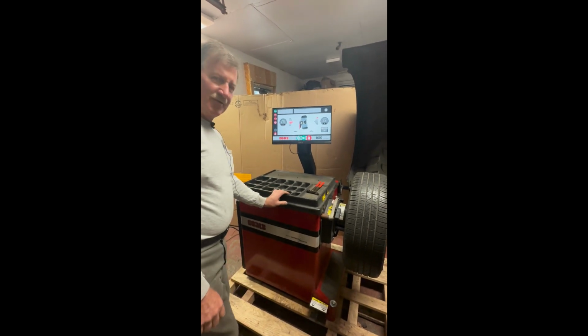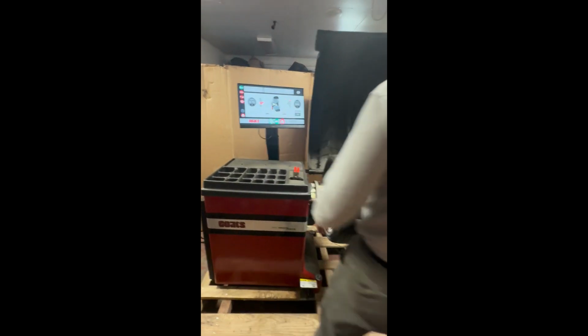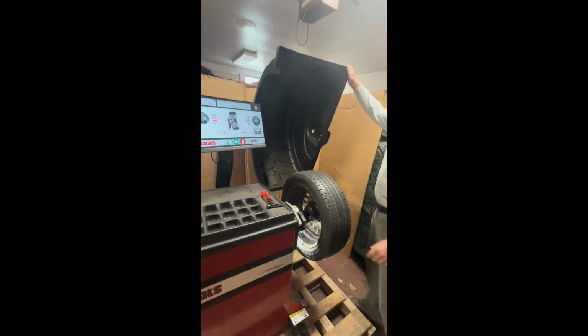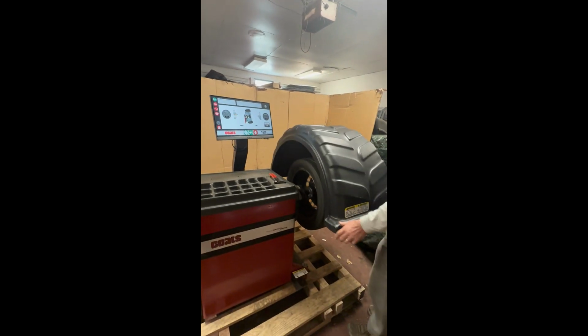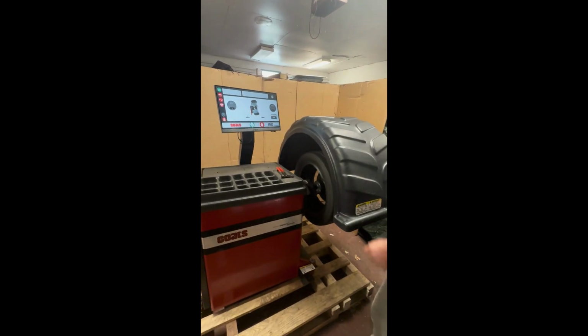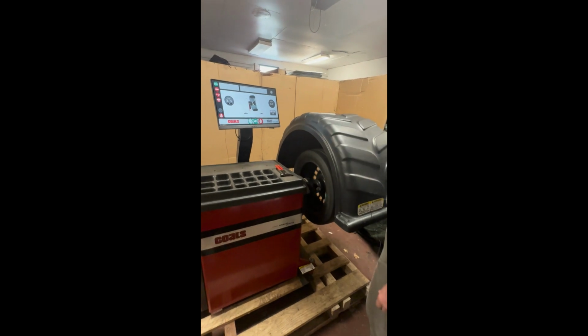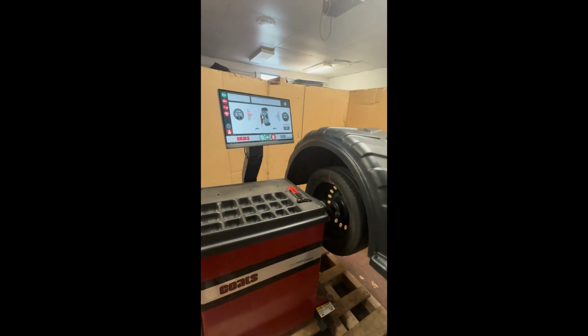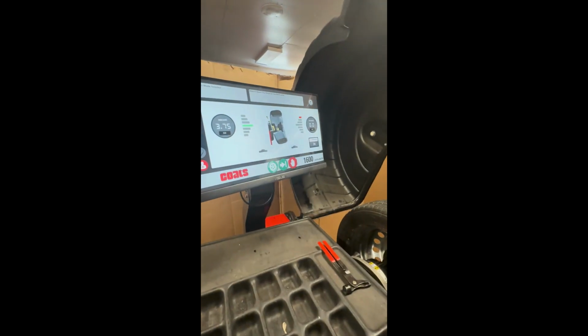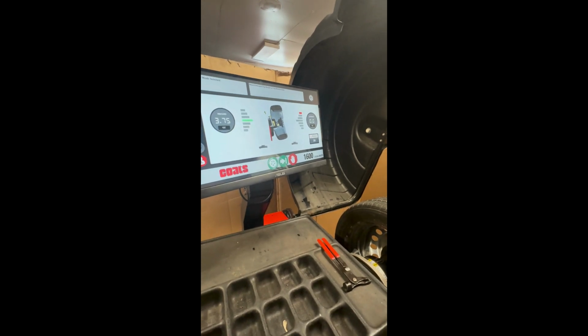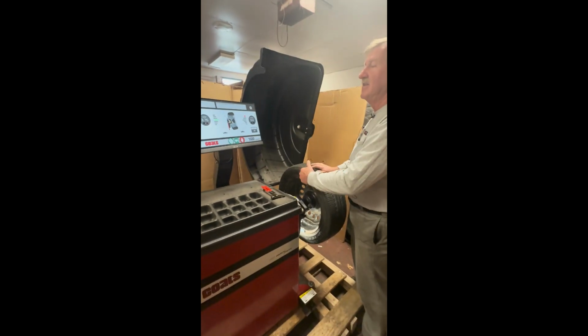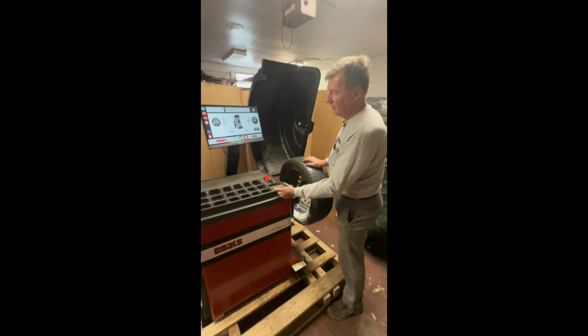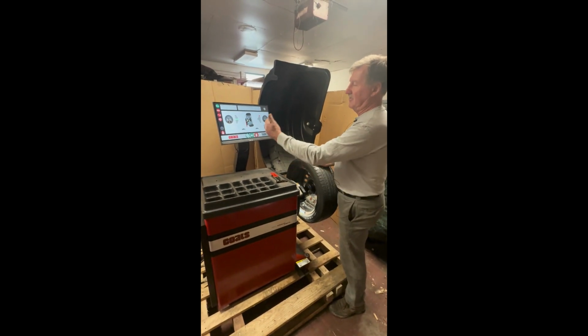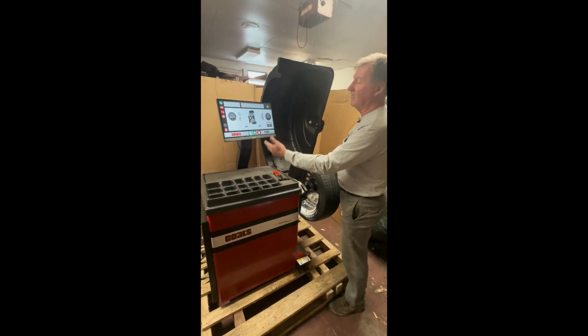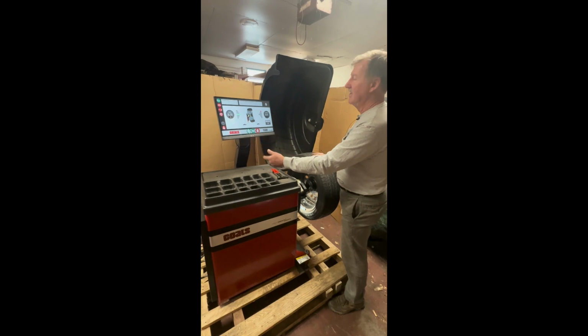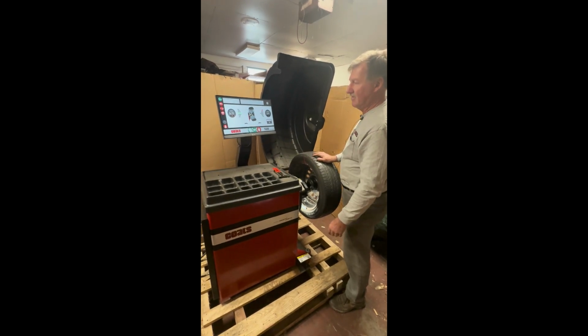But are we? We do need to check our work. So what we're going to do is close the hood. It's just that simple. Let it take a new reading. The reading was 375 and 0, which is acceptable. And the reason why that is because there was that 0.18, if you remember when we started in there. So you're either offsetting it or adding to it, or you're right on. So 375, 4 or 4 1/4 would be acceptable, and the other side should be zeros.